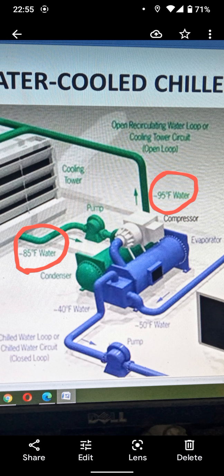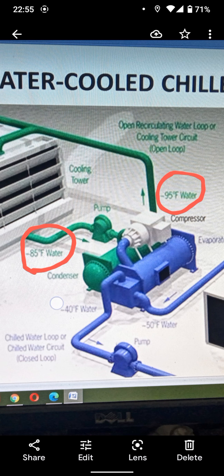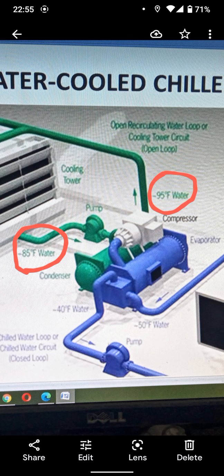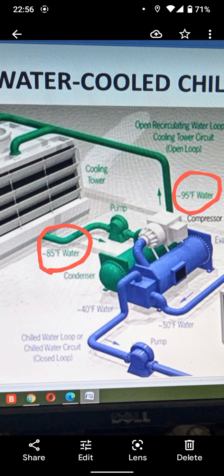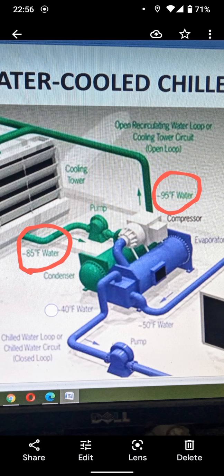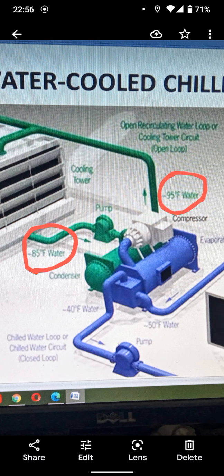So take corrective measures and rectify the problem. Say this plant has been operational for a very long time, there is no surging history, and surging occurs only in the summer season. Sometimes you have to clean the condenser, check the cooling tower and everything, and do chemical treatment of the water, and you can solve the problem. But the discussion of this video is not about any old plant or any maintenance activity.